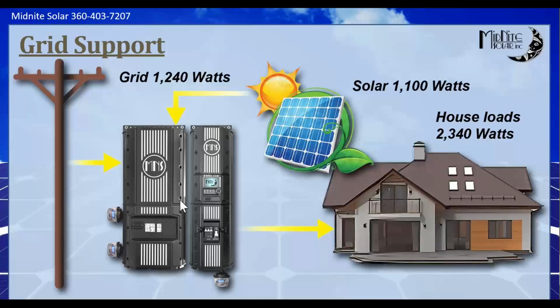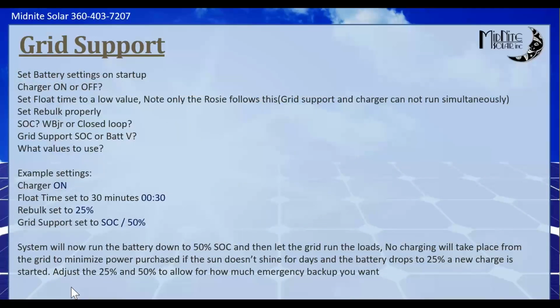Now, if you have your state of charge set to, say, 50%, and the battery's at 80%, then all 2,340 watts will come from the Rosie system. It will take the extra from the battery if the battery is above the target at that moment. And the target can be voltage too — you get to pick that.